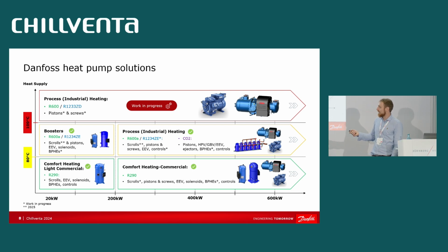For smaller sizes, we see the future with, now, because we already use them, scroll compressors, larger scroll compressors, then going to 300-400 kilowatts, maybe 500 kilowatts. You can also go with several scroll compressors, but you can also go with semi-hermetic piston compressors. For larger capacities up to 1.5 megawatt, we also have our collaboration with screw compressors. They are all visible in Cool Selector. Then what is more interesting is up to 100 degrees centigrade. We have the strategy of dual approval for low GWP refrigerants and hydrocarbons in all of our equipment.